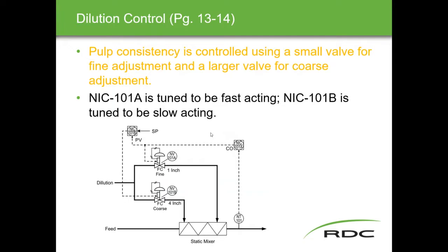For dilution control, pulp consistency is controlled using a small valve for fine adjustment and a larger valve for coarse adjustment — similar arrangements appear with pH control as well. Controller 101A is tuned to be fast-acting, while 101B is tuned to be slower-acting for dilution control, using a consistency transmitter.